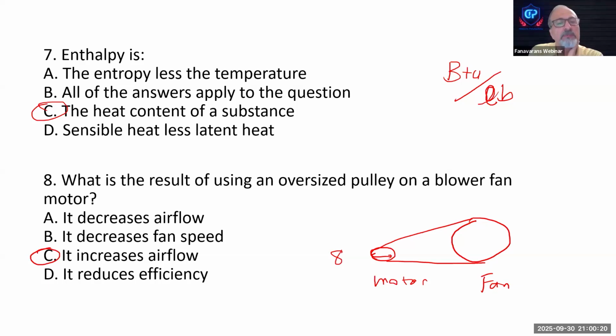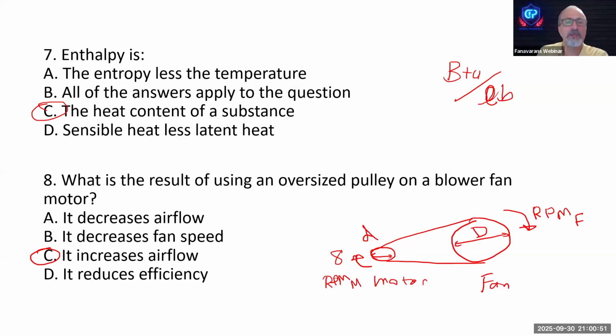Because there's a relationship between the diameter of the pulley on the motor and the capital D, the diameter of the fan pulley. You have the speed of the motor, RPM, and the speed of the fan, RPM. I call this one RPM F and this one RPM M, motor. So the relationship is: diameter of the motor pulley times RPM of the motor equals D times RPM of the fan.